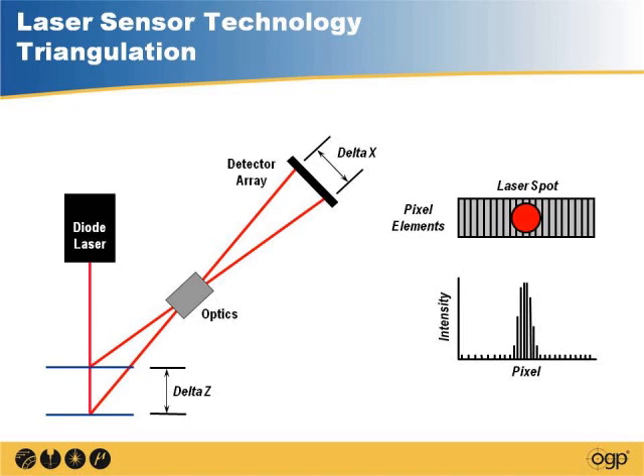Laser sensors themselves are good for measuring surfaces with non-contact. They're very high resolution, very high accuracy sensors, and typically have their highest level of accuracy in the Z orientation, or normal to the path of the laser. One technology relative to lasers is called triangulation, and the concept here is that a laser emits a beam onto a surface, and that beam is then reflected off of the surface into a detector of some sort, and that detector senses where the beam is hitting. There's typically a spot associated with the laser beam that you can see in the upper right graphic, the red spot there. As that moves back and forth on the sensor, that indicates a delta Z down in the lower left, and that's how you determine the Z location of where the sensor is at. So it's a pretty interesting way of making very high accuracy Z measurements.